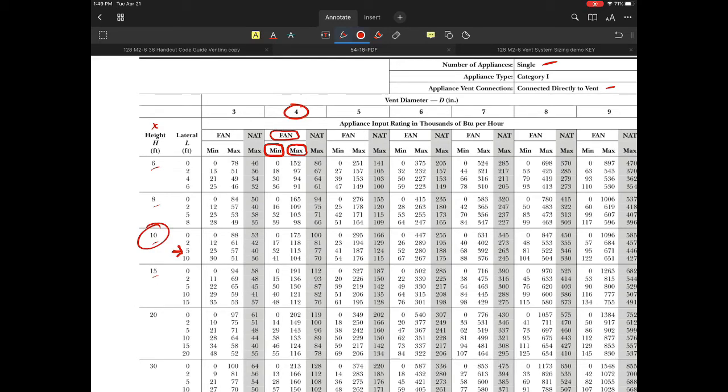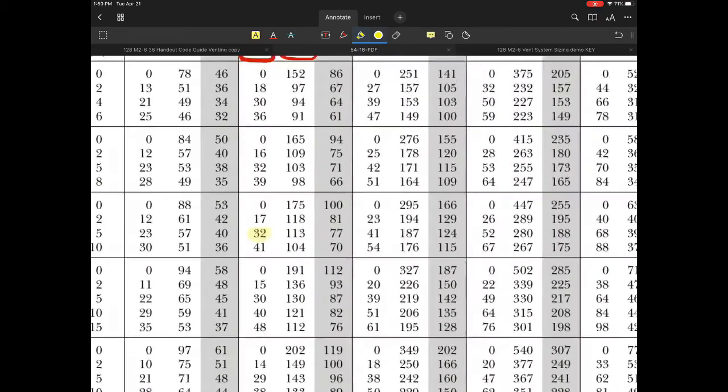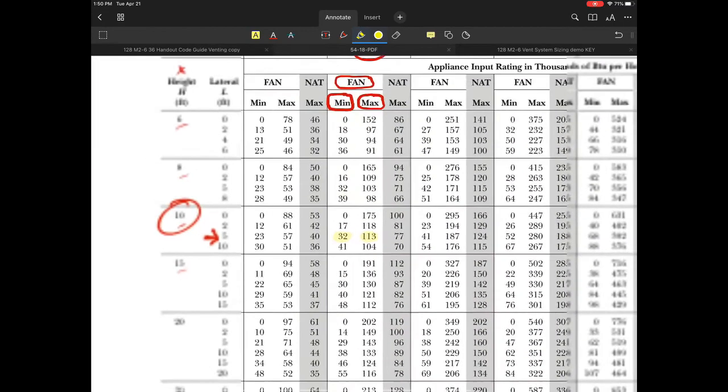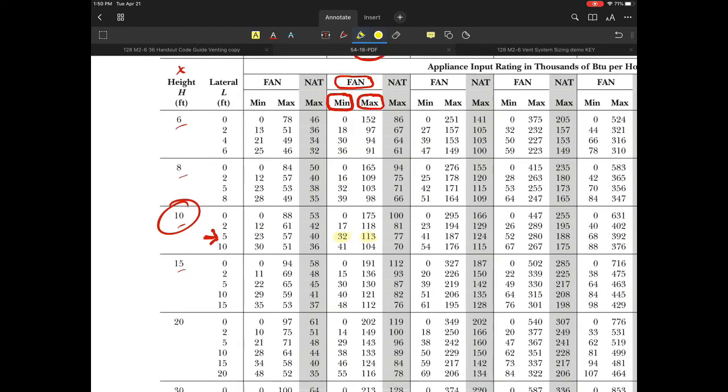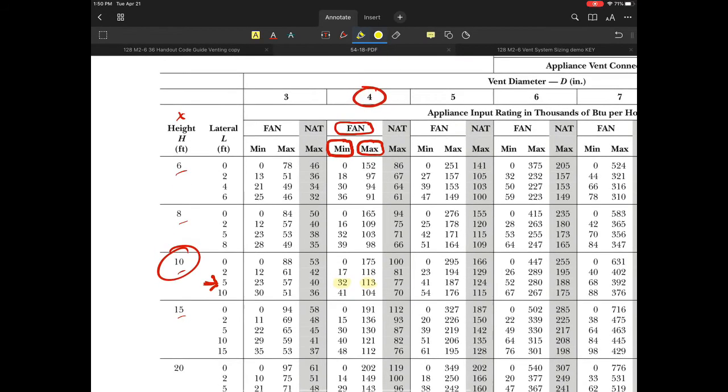At 10 and 5, our low number is 32,000 BTU and the high number is 113,000 BTU. As long as our values are within these numbers, we're in great shape.